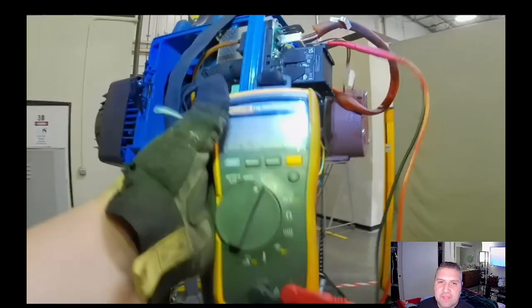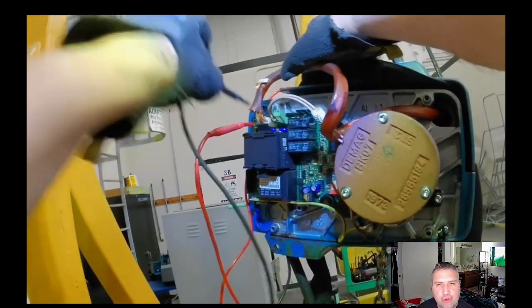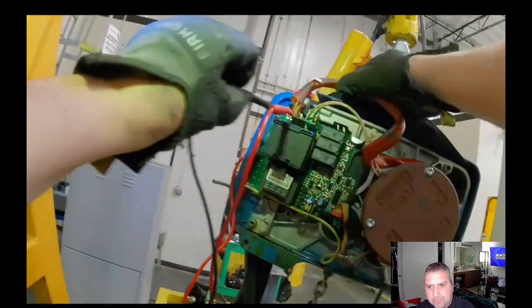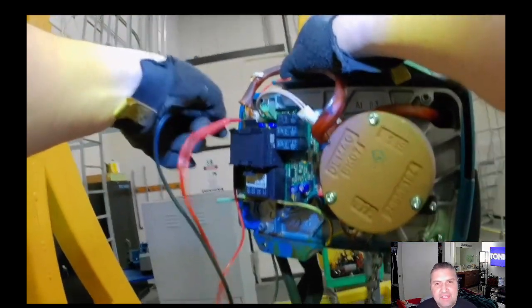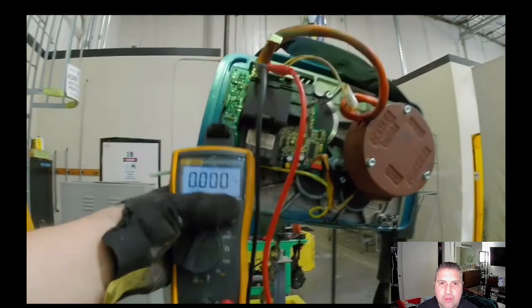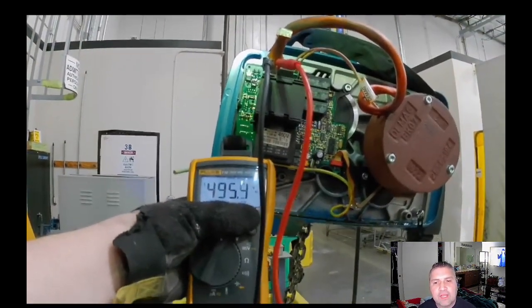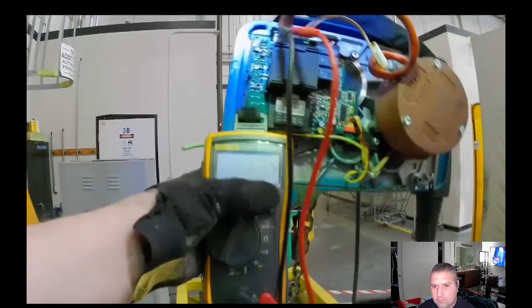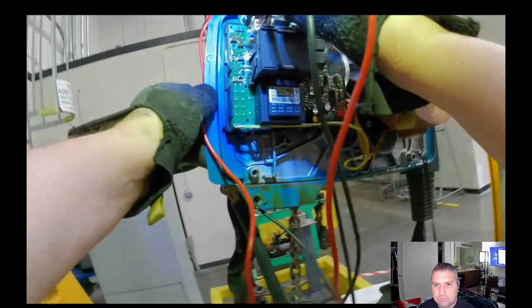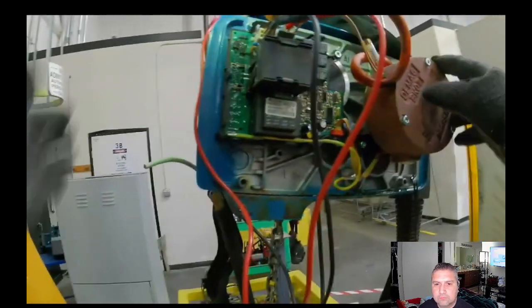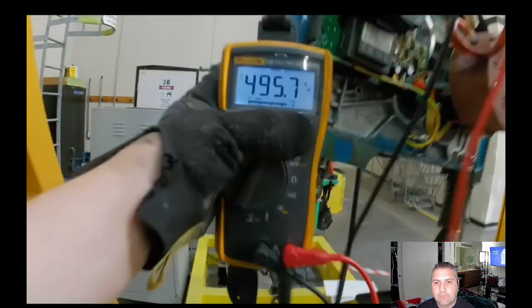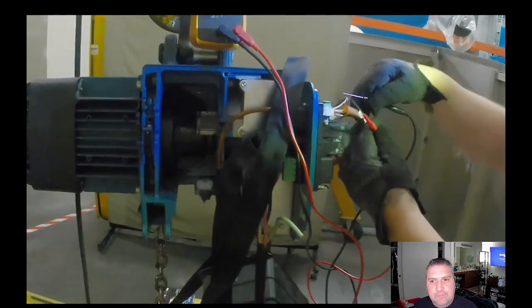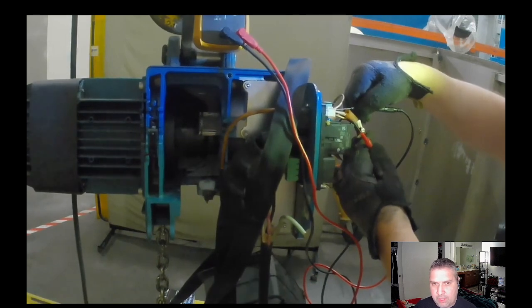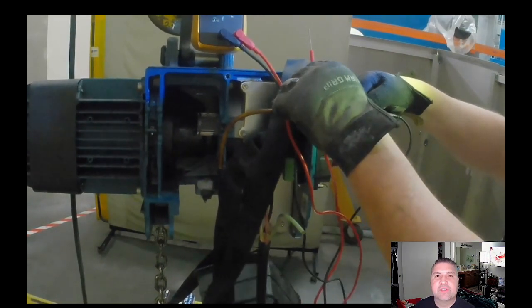So first I'm checking the side that is functional, and I want to see if we're getting any voltage drop across any of those legs. So I'm checking A to C, A to B, and B to C. And we're getting 480 on all three of those. So it seems like that direction is fully functional, which I expected, but I just wanted to get a reference point on what I'm looking for in case I see a severe voltage drop.